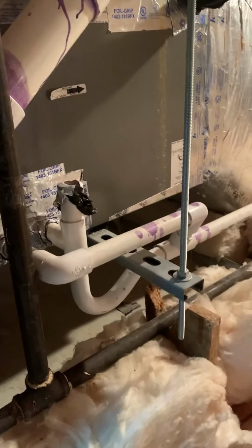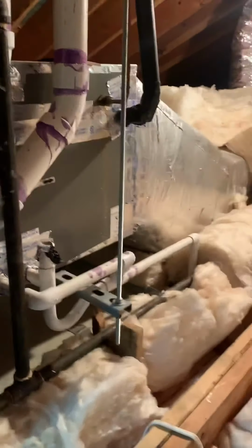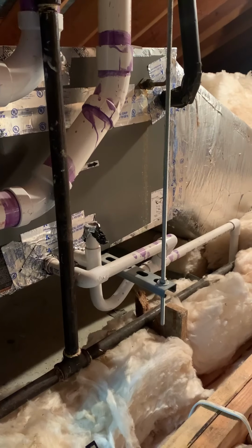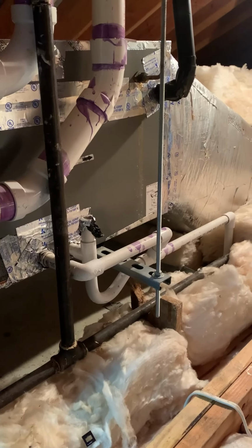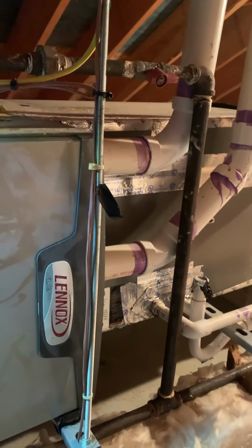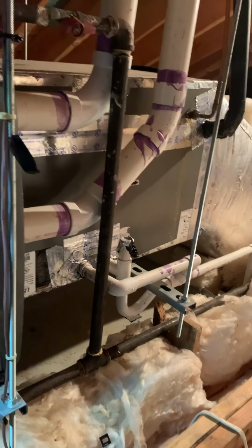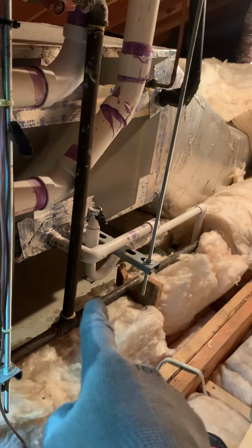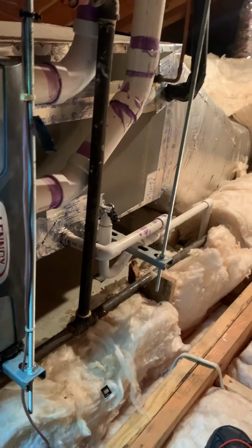I don't know if he did that because his angle iron, his support, is right there, but I don't know. He could have done it differently. Normally when the return and the coil are right next to each other, if the blower assembly is reversed, you have a negative pressure in that coil because it's sucking from the return here, and then you have the coil here, and then the blower's here. So that blower being here is sucking air this way, which is why you need a trap. Because then it will suck the air in through that hole, through the 3/4 PVC, and it won't let the water drain properly. But because the air is going from here through here into the coil, it'll push its way out of here.